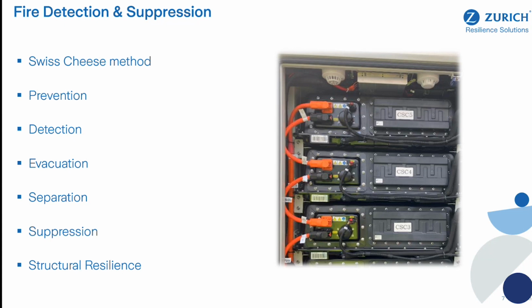Suppression systems. Right, so like I said earlier, there's electrical risks, not so much inside the battery, but auxiliary systems, networking systems for the plant controllers. A fire could develop inside those. So suppression systems such as aerosol generators or, I can't remember the name of the gas used, but gas suppression systems. These could be used to prevent an electrical fire from spreading in one of those systems, maybe on a busbar chamber, but they wouldn't work very well in the event of a thermal runaway event.